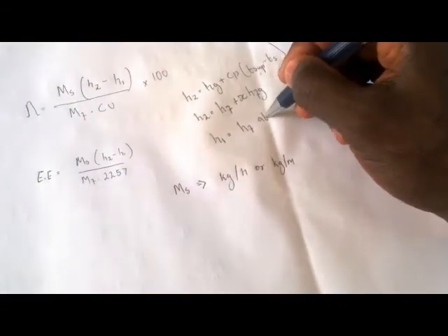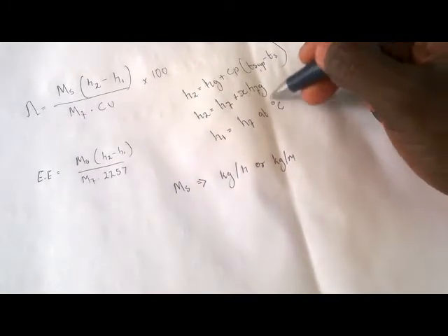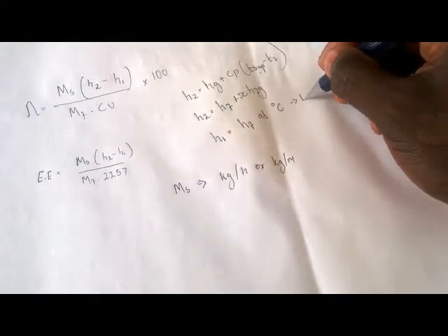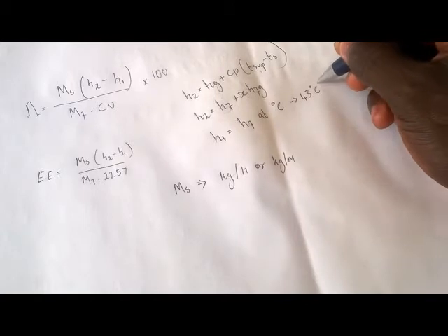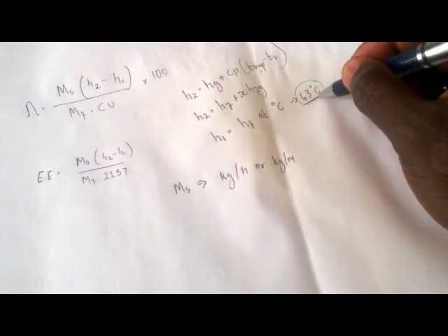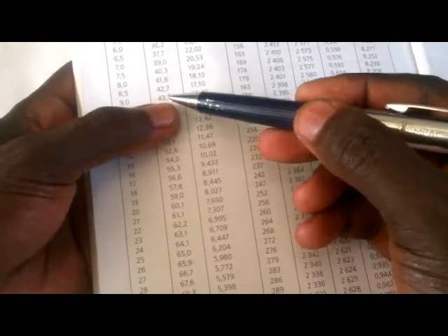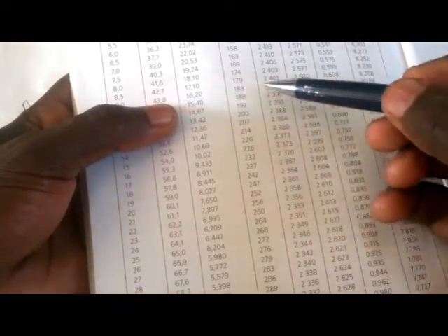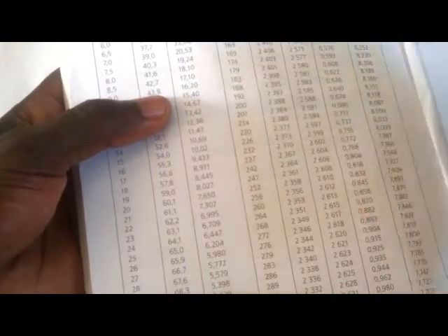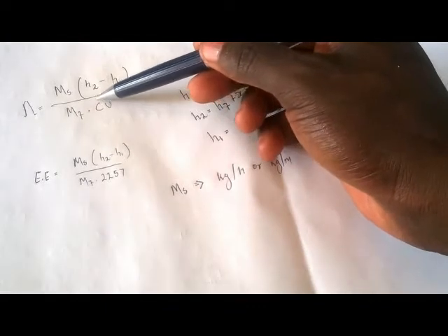Then h1 is the liquid enthalpy hf at the feed water temperature. They will give you the feed water temperature. For example, if the feed water temperature is 43 degrees Celsius, you go to the steam table at 43 degrees Celsius — let's take it as 43.8 — and under that temperature you read your liquid enthalpy, which is going to be 183. This is how you attempt the boiler efficiency calculation.